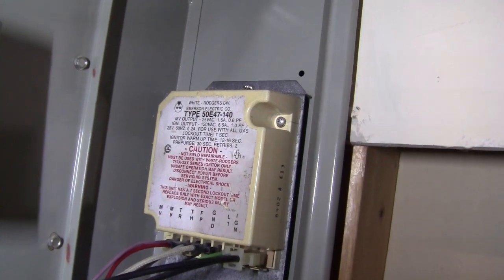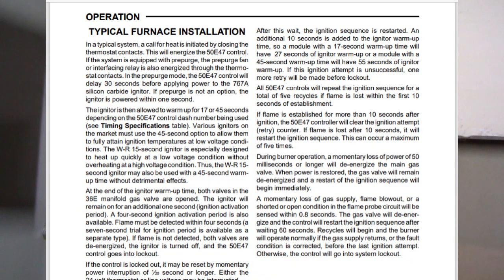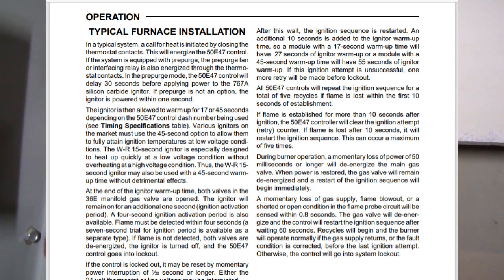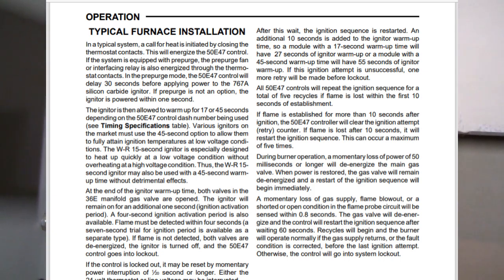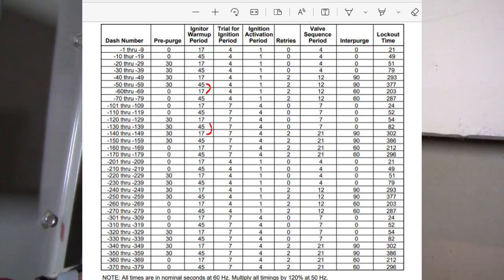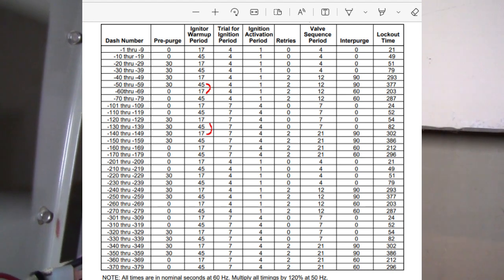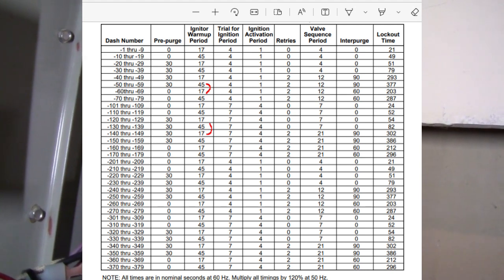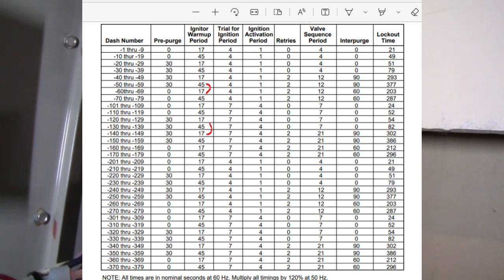It's okay to use this for the 140 to the 60, but there are some other models that have a longer ignite time. The longer ignite time is 40 seconds, and for that one I think you had better find the same model with the same ignite time for the unit. My unit has 15 seconds. The igniter will only last 15 seconds. It won't last 40 seconds. If you have a unit with a 45-second igniter, then you have to find one with a 45-second igniter, or your igniter will not be hot enough to start a fire.